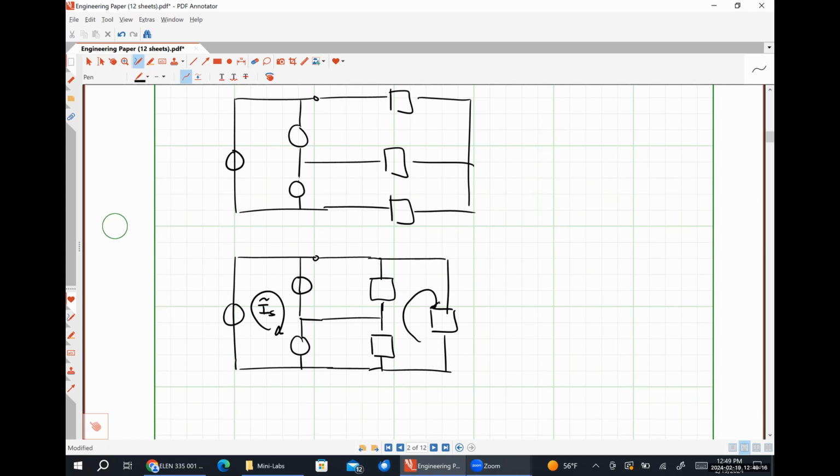From a practical standpoint, it's actually much more likely that you'll have a neutral conductor in that system. And the reason being is that having a neutral conductor there means that the imbalance won't be carried by any of your phase conductors, which means you don't have to size them any larger than they would normally be. Because all of the imbalance will wind up flowing up and down the neutral conductor. And as long as it's not hugely imbalanced, you get to use a smaller gauge of wire for your neutral conductor, which is cheaper.